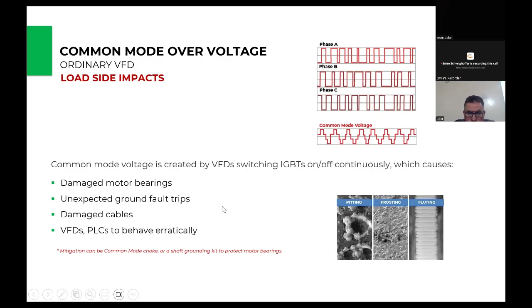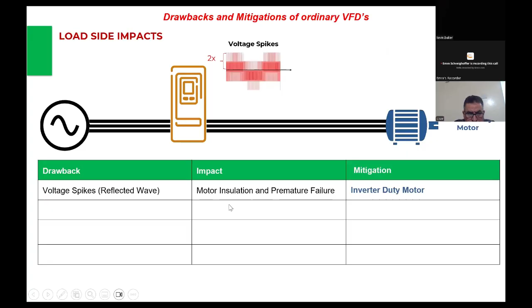There's another component to it, leftover energy called common mode overvoltage. This continues to attack the bearings in your motor as it tries to find its way to ground. You can see an example here of pitting, frosting, or fluting. Frosting is actually the first thing that happens, because every time this energy tries to find its way to ground, the discharge changes the metal in the bearing — we call that frosting. It makes the metal very soft, which can lead to pitting, fluting, etc. Then you end up with ground faults, which are very expensive, and unexpected downtime. So if you've got critical applications, this is where we want to make sure we're mitigating all of that.